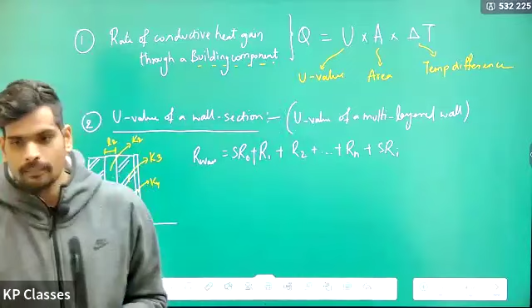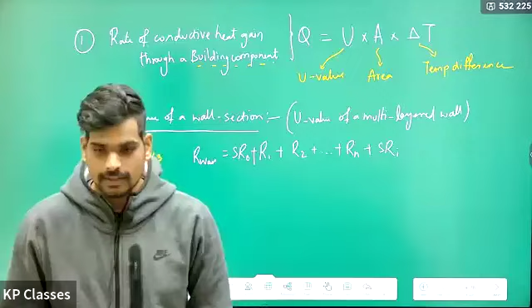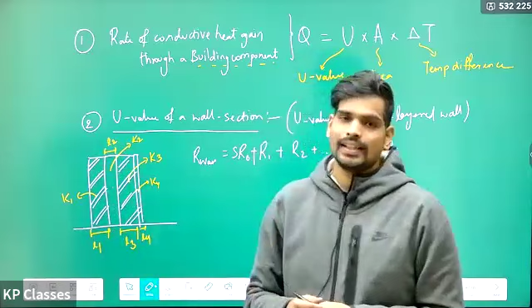Rather, you calculate the R value, the resistance of the wall, as the surface resistance of the outside surface, plus the resistance of all the layers, plus the surface resistance of the inside surface. The resistance of any layer is calculated as L by K. For example, the resistance of the first layer will be L1 by K1. The resistance of the second or any nth layer will be Ln by Kn. L by K is called the resistance of that particular layer.